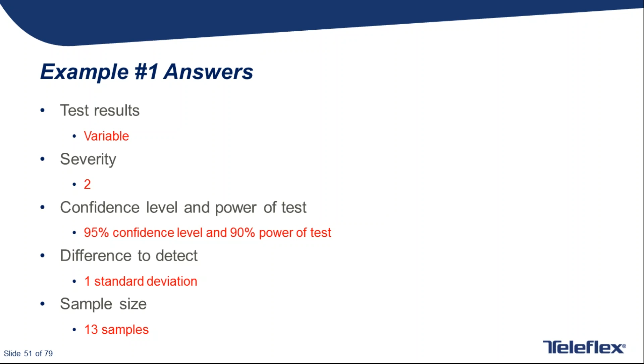So then using that confidence, power, and difference to detect, which we're assuming is 1 in this case, the sample size is 13. For a severity of 2, the required confidence level is 95% and the reliability 90%. So in this case, after we do the testing with 95% confidence and 90% reliability, the insertion force should be less than 50 grams. I kind of raced through that example, but this pretty much summarizes what the answers are, what questions you need to answer in order to start to do the testing. So 13 samples.